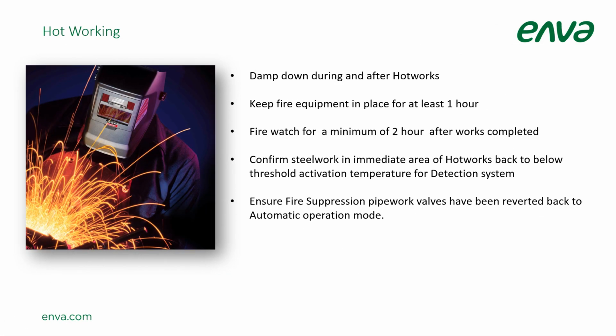Damp down during and after hot works. Keep fire equipment in place for at least 1 hour. Fire watch for a minimum of 2 hours after works completed. Confirm steel work in the immediate area of hot works is back below the threshold activation temperature for the detection system. Ensure fire suppression pipework valves have been reverted back to automatic operation mode.